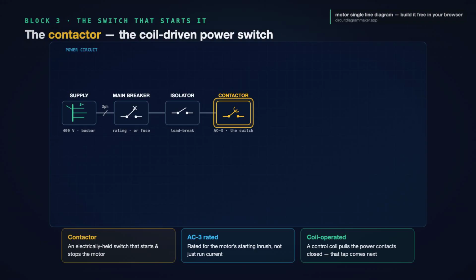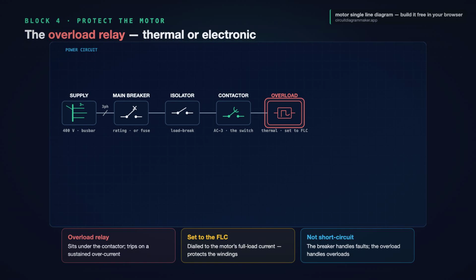Block 4, the overload relay, thermal or electronic. The overload sits directly under the contactor in the same run of the line, and it does one thing. It watches the current and trips if the motor pulls too much for too long. On the diagram, it is a small block with a thermal element inside it. Here is the part people get wrong. The overload is not short circuit protection. That was the breaker's job. The overload guards against a slow, sustained overcurrent, a jammed load, a failing bearing, a lost phase.